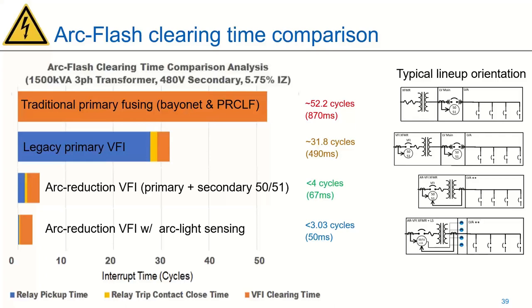And really, say you had your pole-mount fuse cutout: because those secondary settings are so much tighter, it is going to be coordinated first. That's something you could easily trip offline well before you would have to wait for that primary fuse. Whether it's your own primary fuse or a utility fuse feeding the transformer, you don't want to bother the utility. You'd rather trip your own feeder offline. That's really some of the intent behind that as well.